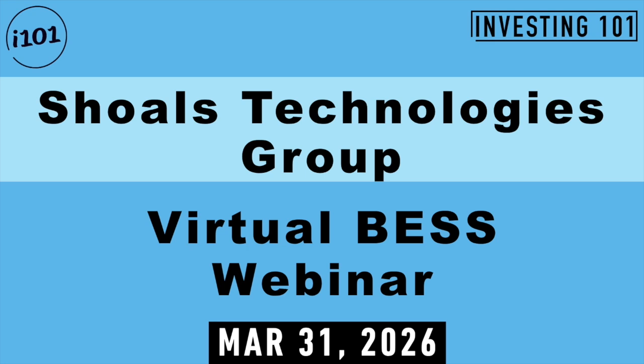We announced this at Investor Day, so I'm not disclosing any material non-public information, just refreshing it. We're introducing a product that fits nicely in between the two. We're using our BLA, our big lead assembly that's been in solar fields for over a decade, and testing it for the AC environments you see within a data center. Envision the busway going above the row of racks, with BLAs in a cable management configuration running along the row, and the drops that would normally go to a solar string instead feeding into a tap-off box that goes down into the rack. We believe the system we're developing will substantially save on labor and can be turned around very quickly for a specific site—no more long lead times for busway.